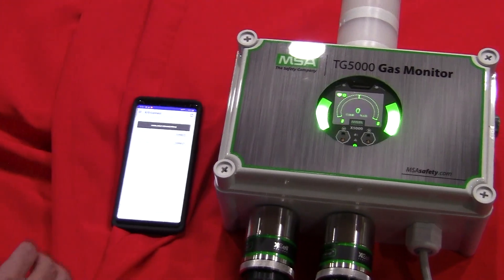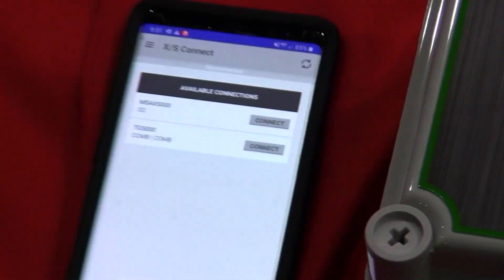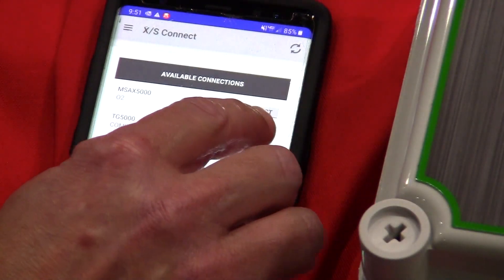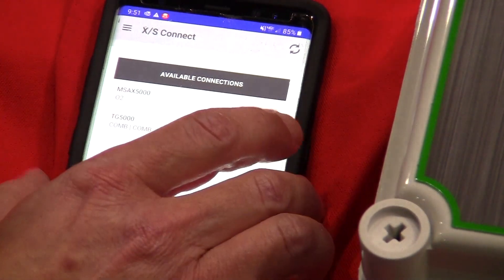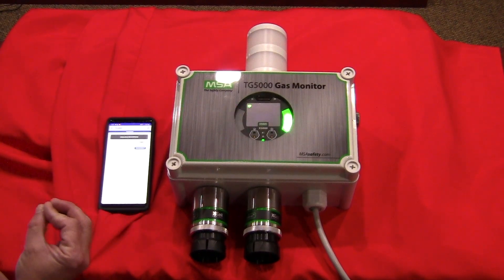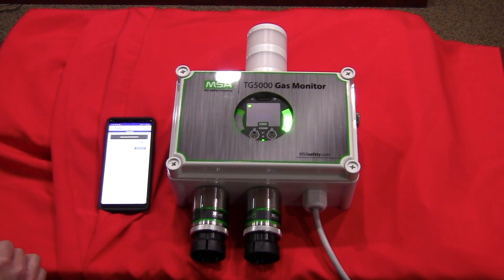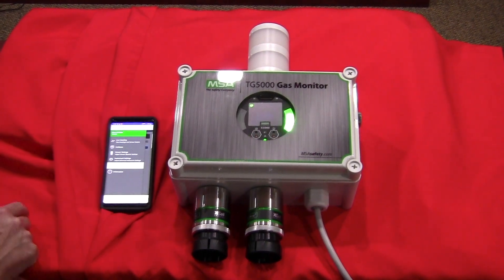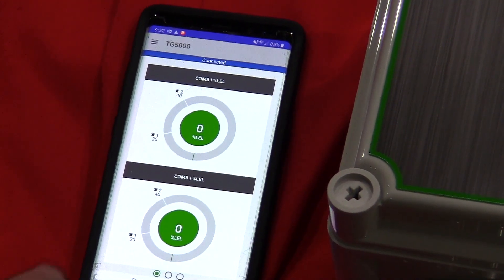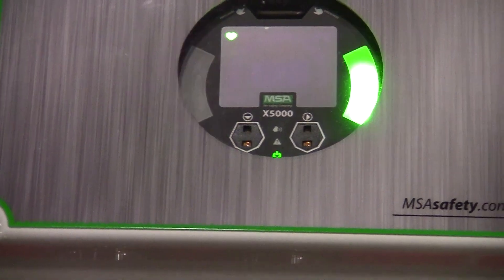Now we're going to look at the MSA X/S Connect app and show you how easy it is to interface with the monitor via your cell phone. I have the app open on my phone and I'm going to select the device I want to pair with. One phone can only pair with one controller at a time — in this case it's the TG5000. As I begin the pairing process, the LEDs will flash. During initial setup it will ask for pairing codes, which I have disabled so we can quickly demo the unit. Once connected and paired, live gas readings will mimic what the display shows, and I can be up to roughly 70 feet away from the monitor via Bluetooth.